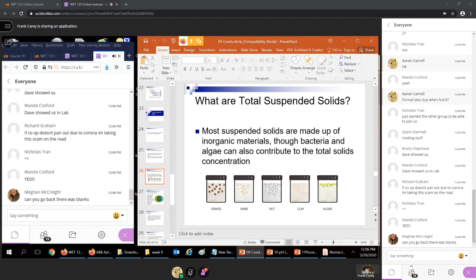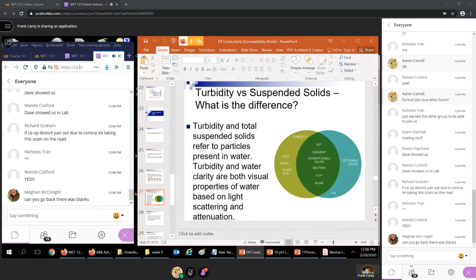So we quite often in the water industry use turbidity to give us an idea of the total suspended solids, but of course that is not accurate, and we need other instruments that give us that capability. So we know the definition of turbidity. Usually for a nephelometer, it is measuring the scattering of light, and generally at 90 degrees.